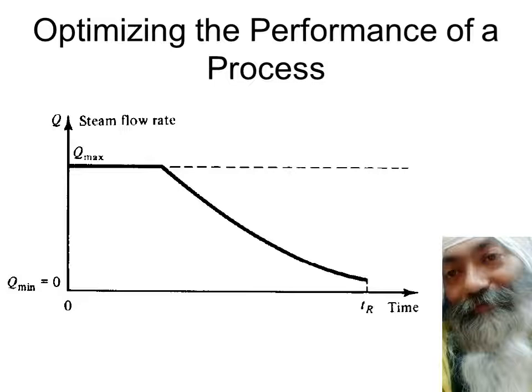This is how the steam flow rate Q should change: Q should be maximum up to a certain amount of time, as calculated, and thereafter the steam flow rate should gradually be reduced. This profile — its shape, its timing, its final time — is all calculated if you know the dynamics of the process well. The controller's job is to regulate this flow rate and follow this profile so as to maximize the profits. It is not for safety, not to suppress disturbance, not to ensure stability — but to follow this profile.